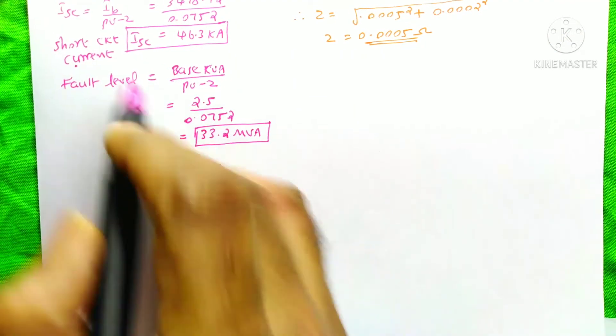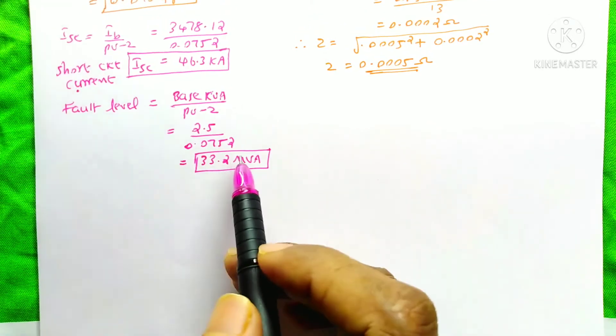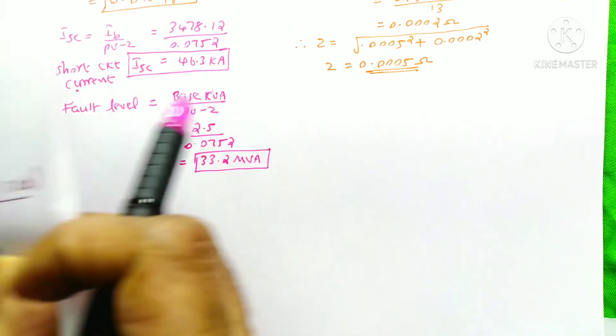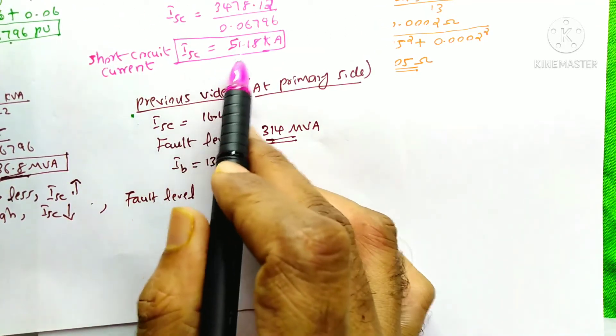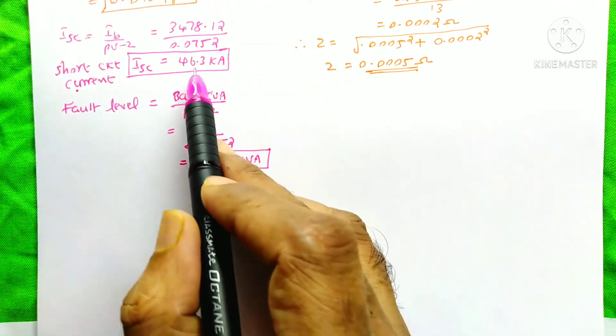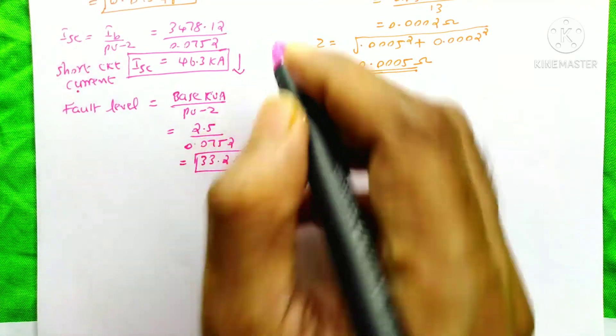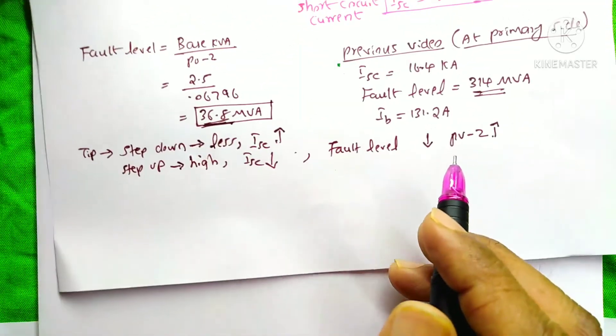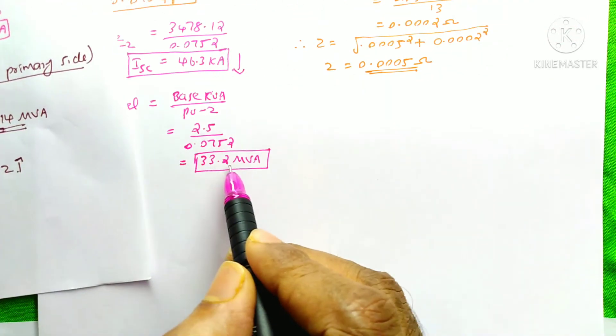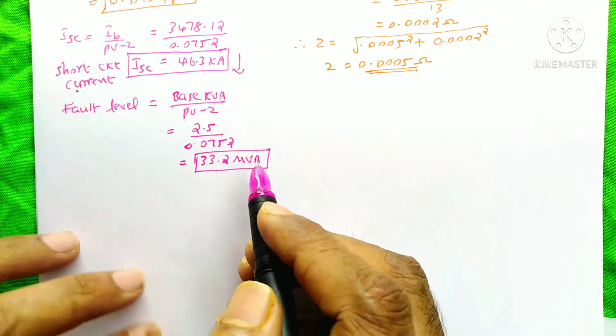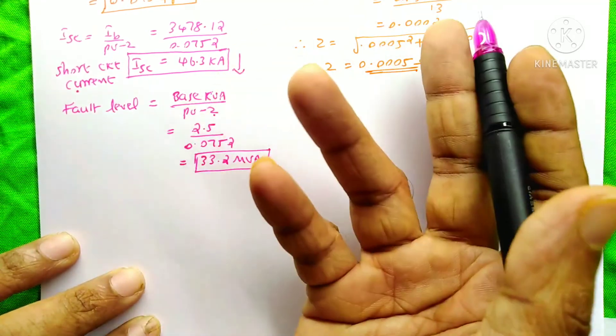Both the short circuit current and the fault level have decreased when compared to the secondary of the transformer. At the secondary, the short circuit current was 51.19 kA, but here it is only 46.3 kA. The fault level at the secondary was 36.8 MVA, and here it is 33.2 MVA. This is all because of the increase in per unit impedance due to the cable.